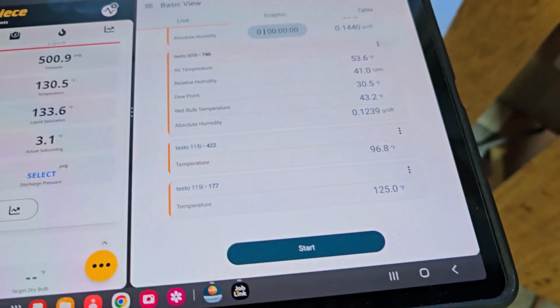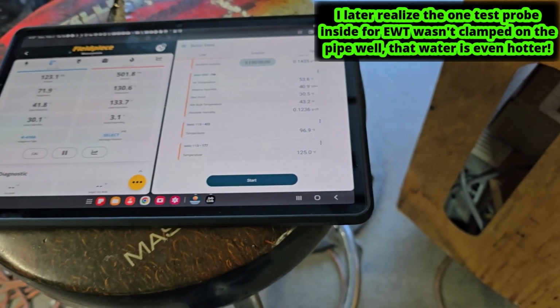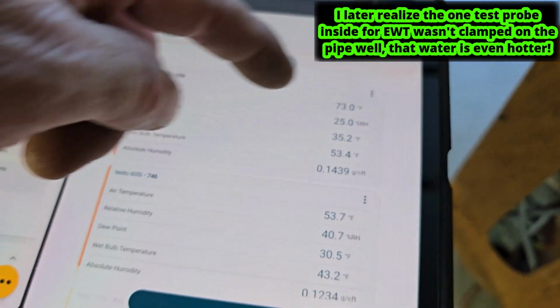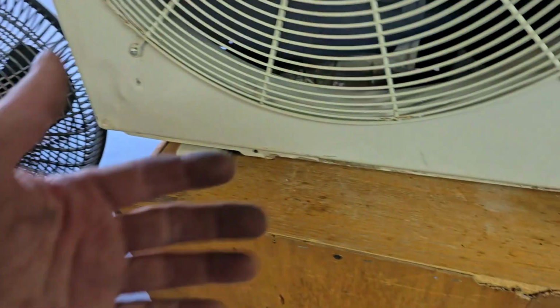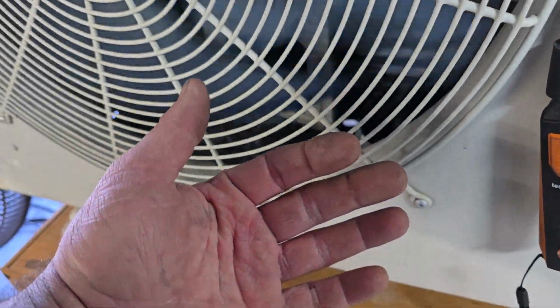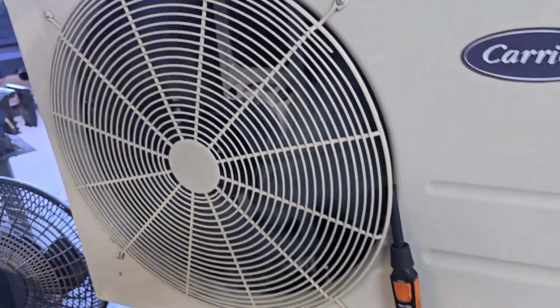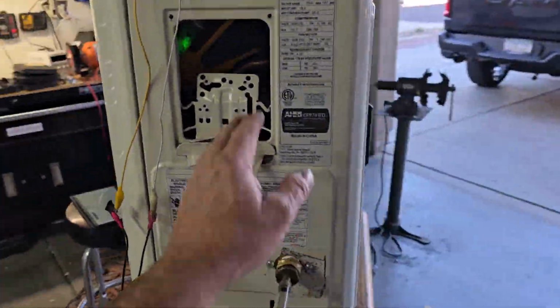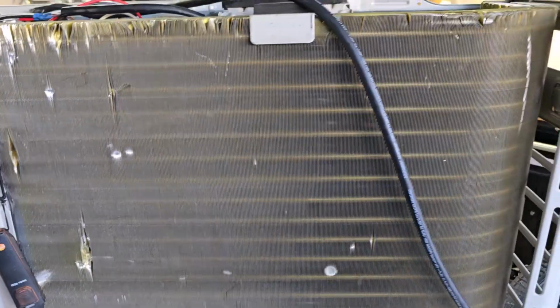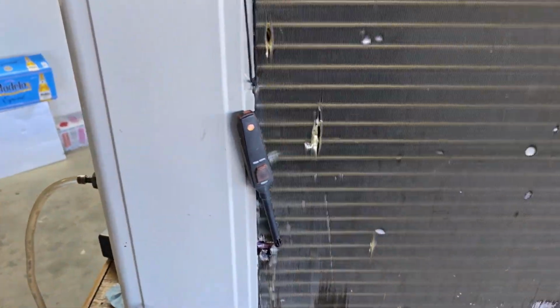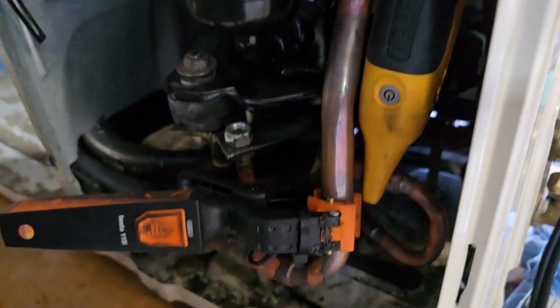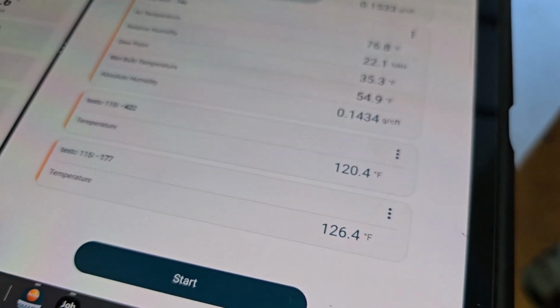That water in that bucket, uninsulated bucket, mind you, is just heating right up. Back to the air temperatures, 73, 53. So it's cooling the air right here from that evaporator. Pretty cool. Once I get this all together, I'll have to clean it up a little bit. It'll look like something. I just moved the probe. This Testo was on this elbow up here, so it wasn't even touching all the way. So once I got it on there, you could see the water temperature just shooting up.